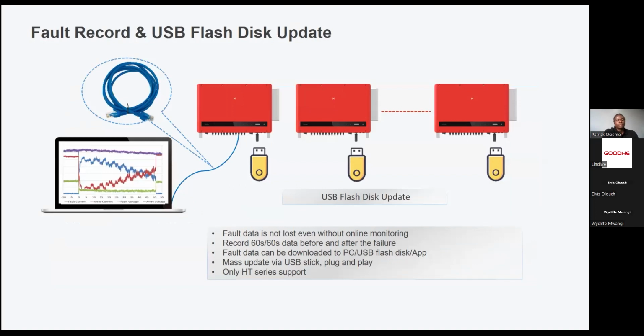In case you want to do a USB flash update for a single device, this is an optional feature, because the same can be done using the SEC 1000 for batch updates. But if you have single units, then this is an option for updating your firmware. So you can do a localized update or a remote update of your inverters or PV systems. Mark you, the recording interval for inverters is 1 minute. That's how frequently we monitor our systems, just to help you with the troubleshooting of your plants.